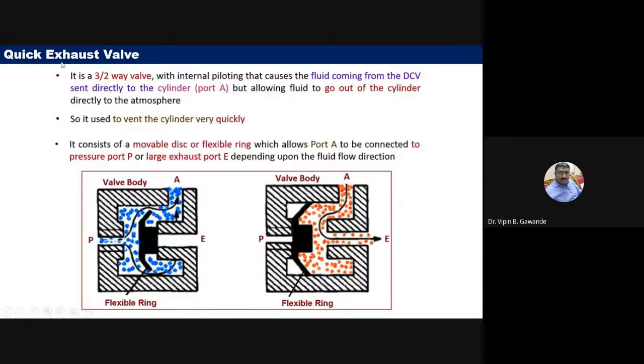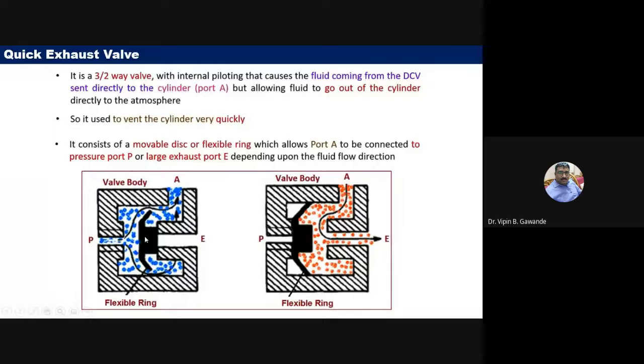The next topic is the quick exhaust valve. As the name indicates, its function is to remove pressurized air quickly from the pneumatic system. It is a 3/2-way valve — three ports (P for pressure, A for the actuating cylinder, and E for exhaust) and two positions. A flexible ring inside shifts between two positions, left and right.